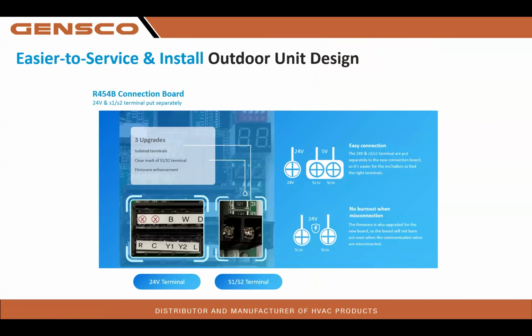Outdoor unit. We've already discussed this. We can go full 24 volt or communicating S1, S2. If we're going to go fully communicating, that is a 5-volt bias DC signal landed on S1, S2. And of course, our 24-volt connections are right here. RC, Y1, Y2, L for alarm. We're not going to need BWD.